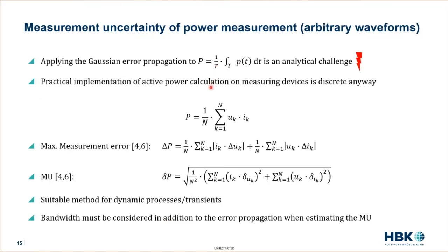But what is done on the measurement system, if we look at how it is calculated over there, is the discrete representation of an average. For each sample time, we measure voltage and current and multiply them. This gives you the instantaneous power value of this sample. And then we sum up over n samples and divide by the number n, which is then again the average. Of course, n depends on the ratio of sample frequency to fundamental frequency if we link the averaging to the fundamental cycle of the electric signals. But it can also be a timed average. So this is not restricted in this formula. It's only a mean value.